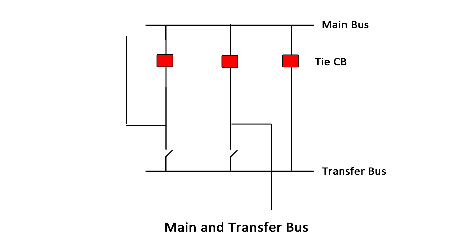The transfer bus is energized and the isolator nearest the transfer bus of the breaker to be maintained is closed. The circuit breaker to be maintained is now opened, isolated, and removed for maintenance. The circuit under maintenance is transferred to the transfer bus.